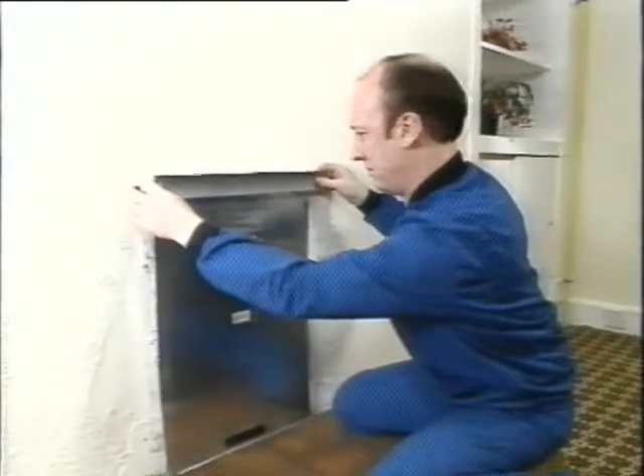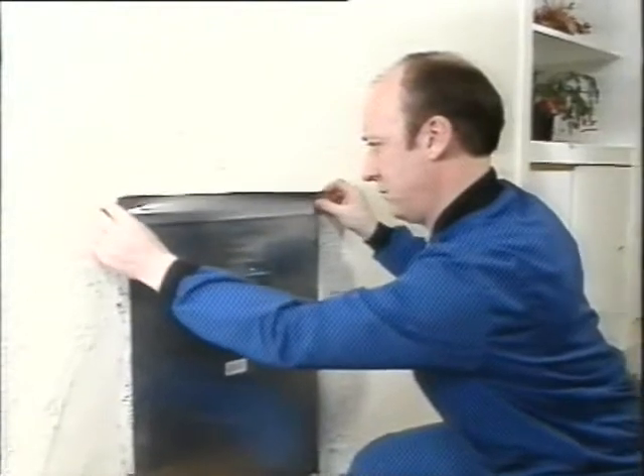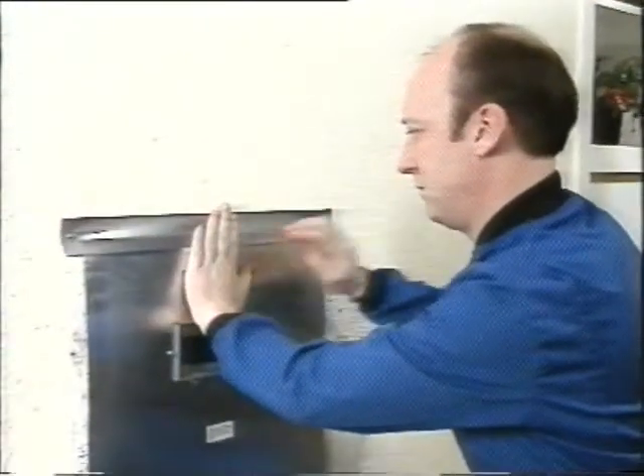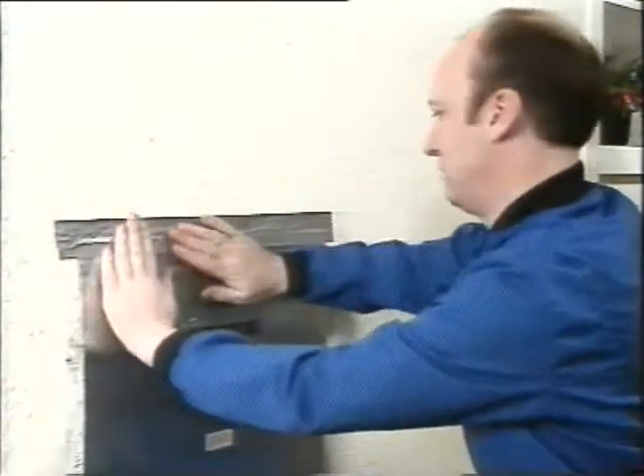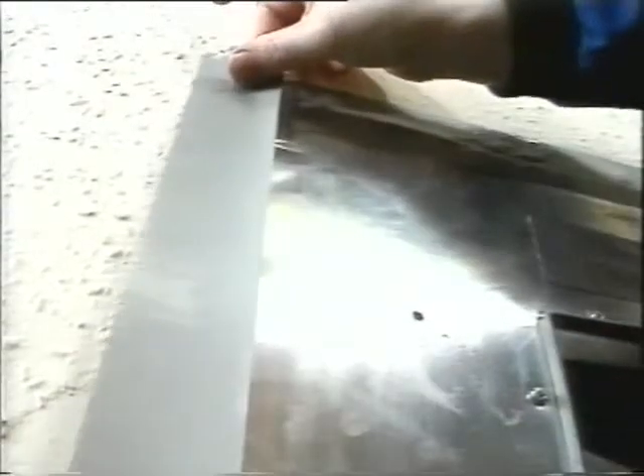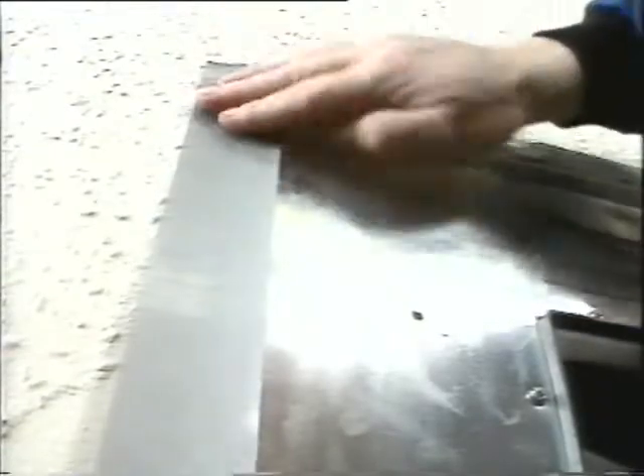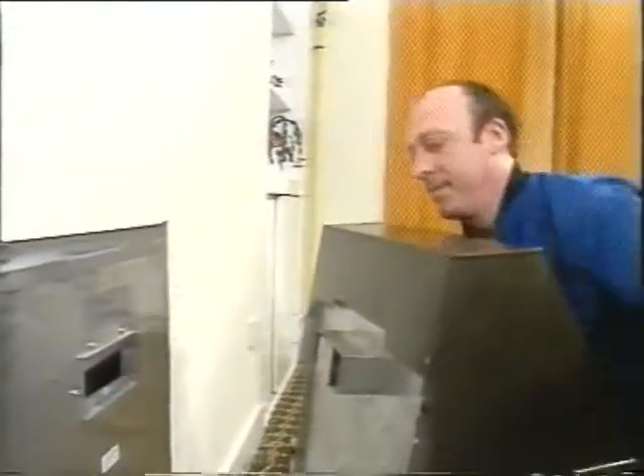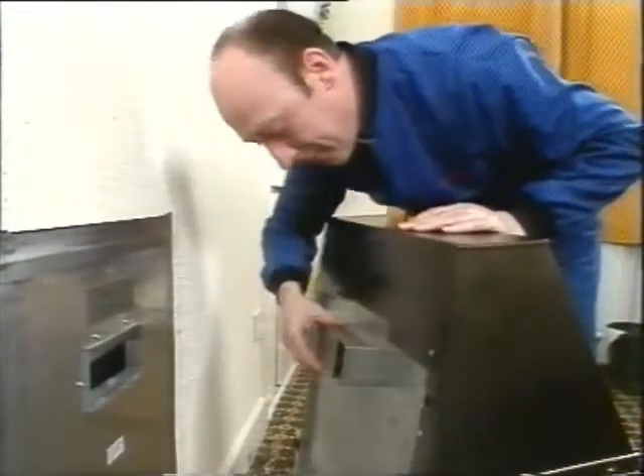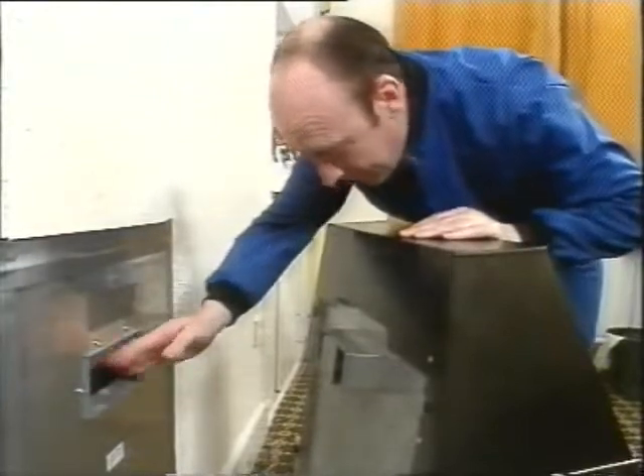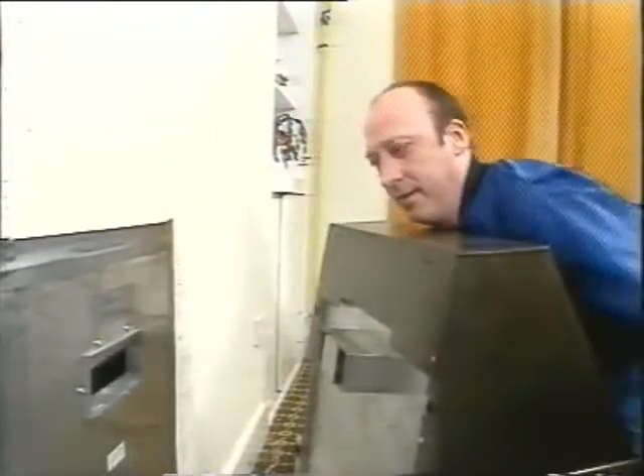The tape or material used to seal around the edges of the closure plate must be able to withstand temperatures up to 100 degrees Celsius. It also has to be flexible enough to effectively seal uneven surfaces like stone. The size, type and location of flue spigots are critical. The manufacturer's instructions will give full details, so check them thoroughly before installation.